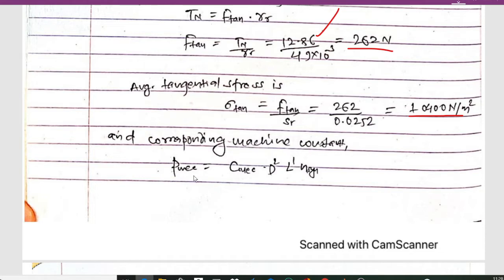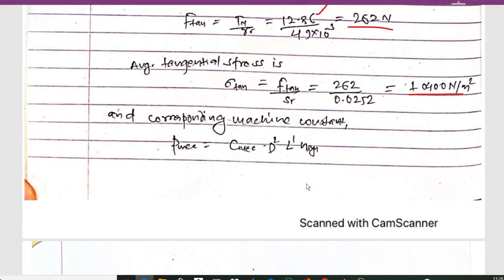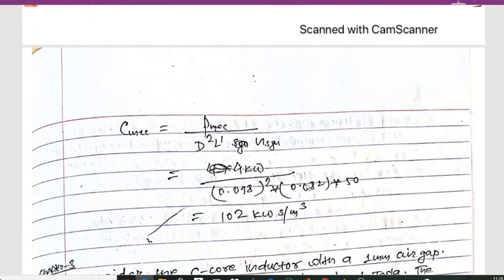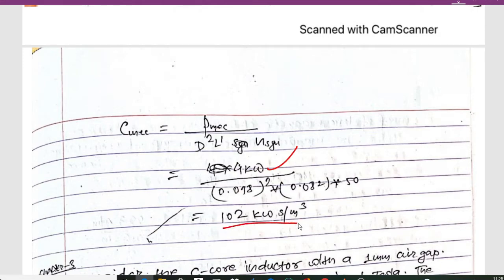The corresponding machine constant is given by the formula P_mech = C_mech · D² · L' · ns. Rearranging, C_mech = P_mech / (D² · L' · ns). With P = 4 kW, D = 0.098 m, L = 0.082 m, and ns = 50, we get C_mech = 102 kW·s/m³.